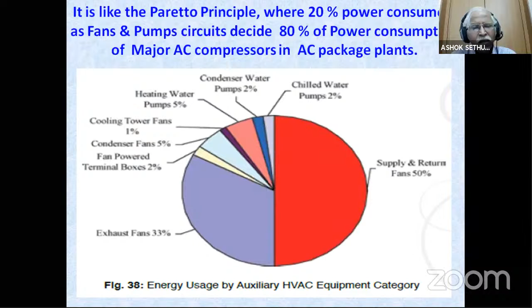Going by the Pareto principle, 20% of the power consumers in a given system dictate the terms for 80% of the power consumption of the main compressor. For example, in a split AC, if the evaporator indoor coil or the outdoor coil gets totally choked or heavily dusted, the compressor, instead of running for 8 hours, will run for 12 hours. The peripherals, auxiliaries, or subsidiaries decide the main compressor's hours of operation.